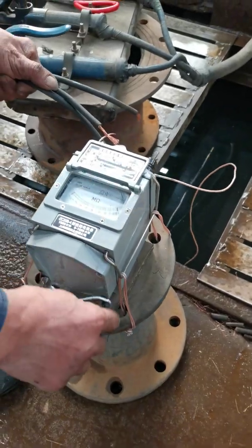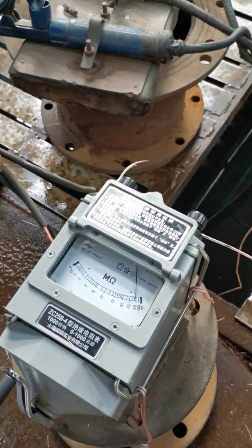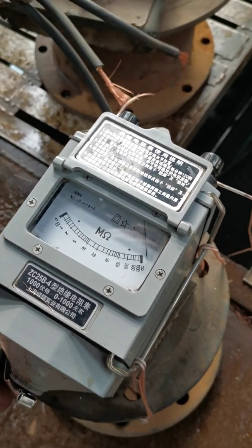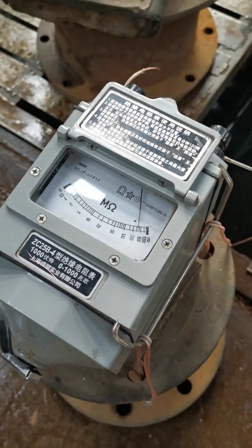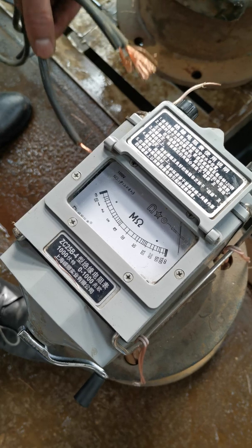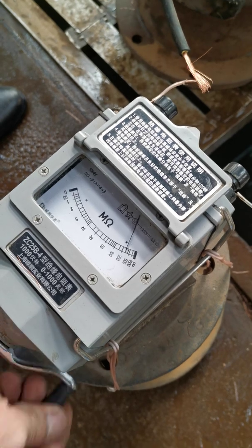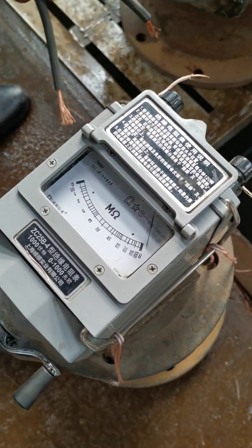We will check the insulation of the motor one more time. After the unit pump test, we will test the insulation once more. You can see the insulation has now reached 1000, and it's OK. So the motor is OK. The pump is OK.